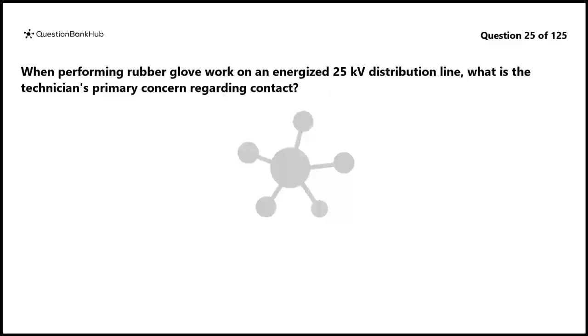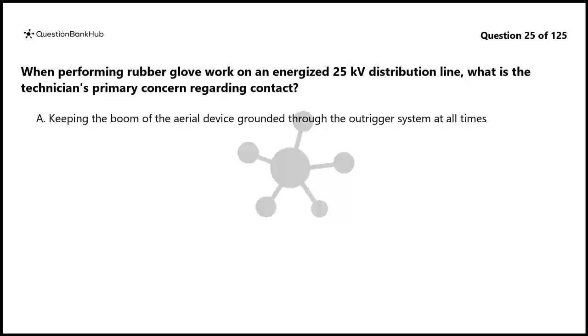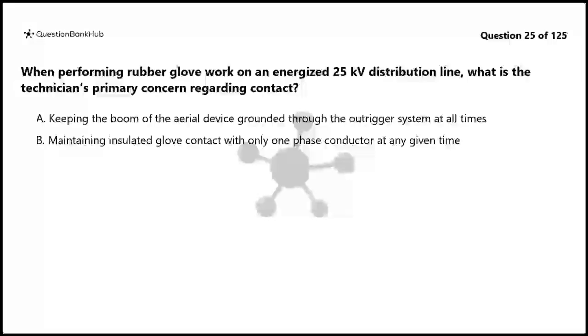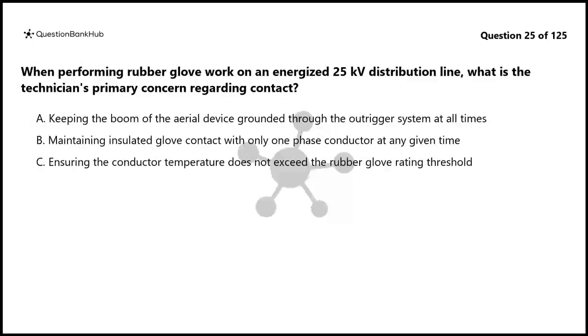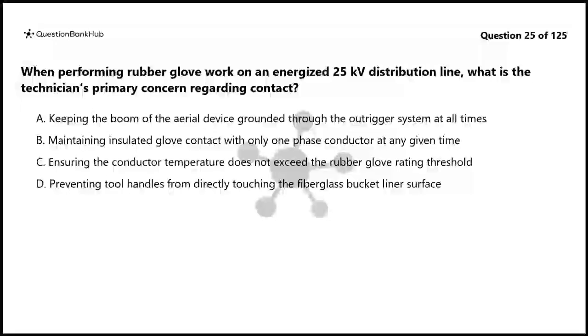Question 25. When performing rubber glove work on an energized 25 kV distribution line, what is the technician's primary concern regarding contact? A. Keeping the boom of the aerial device grounded through the outrigger system at all times. B. Maintaining insulated glove contact with only one phase conductor at any given time. C. Ensuring the conductor temperature does not exceed the rubber glove rating threshold. D. Preventing tool handles from directly touching the fiberglass bucket liner surface.